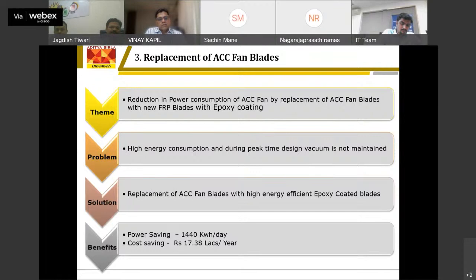Our third best practice is replacement of ACC fan blade with epoxy coating AFA FRP blades, which are lighter in weight and highly energy efficient, through which we can achieve a saving of 1440 kWh per day, which resulted in a saving of 17.38 lakh per annum, sir.